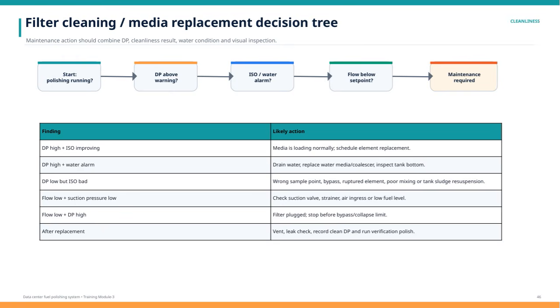When flow is low combined with low suction pressure, it's essential to check the suction valve, strainer, air ingress, or possibly a low fuel level. And if flow is low but differential pressure is high, this points to a plugged filter. So stop the operation before reaching the bypass or collapse limit. After replacing filter media, remember to vent the system, check for leaks, record the clean differential pressure, and run a verification polish to ensure everything is functioning correctly. Together, these steps help keep the fuel polishing system running efficiently and maintain fuel quality.